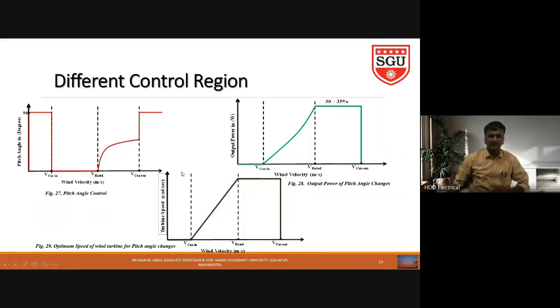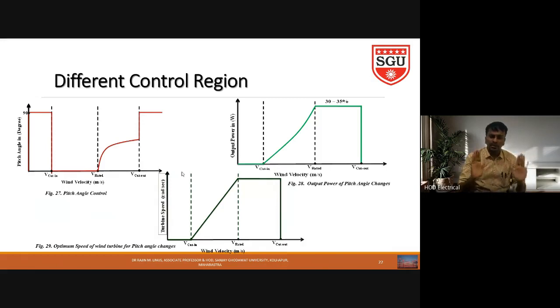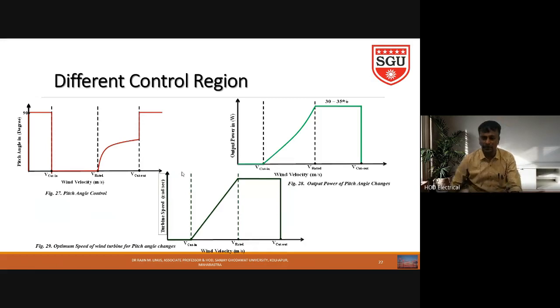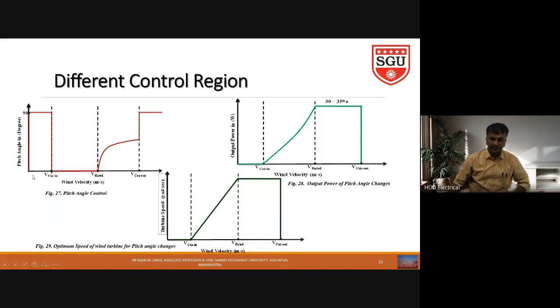Let me now explain with the diagram when and where we use pitch angle control. On the x-axis, wind velocity is increasing from cut-in speed through rated speed to cutout speed — V_cut-in, V_rated, and V_cutout. What is V_cut-in? Below V_cut-in, the wind velocity is so low that the power production from the wind turbine is not sufficient to drive the electrical machine as a generator.